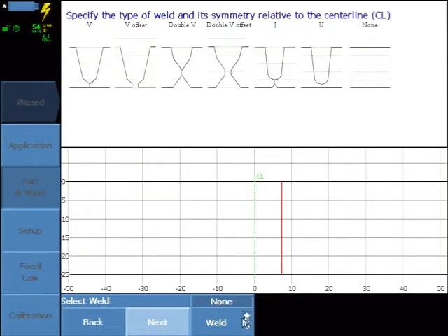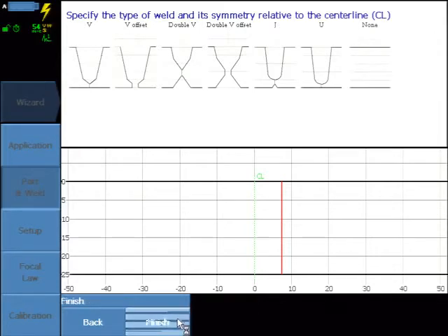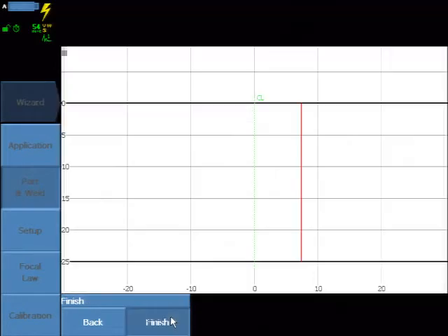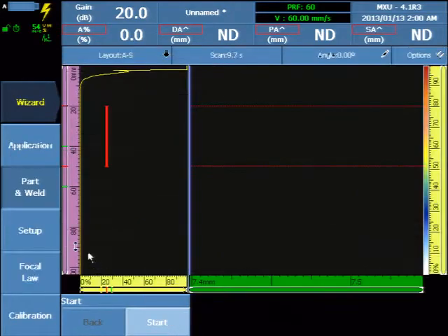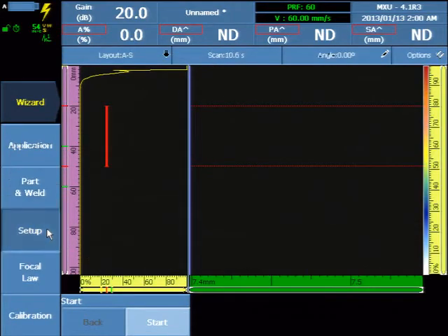No weld is visible in the TOFD B-scan, so you can finish and continue to the Group Setup Wizard.